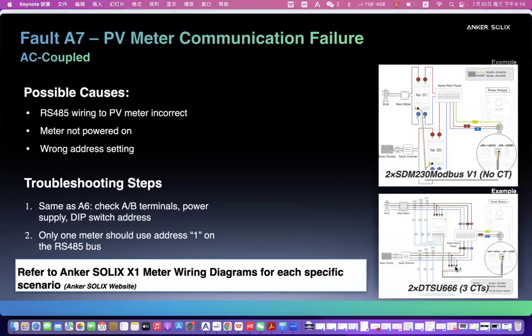It will show A7 when you connect it wrong, because we have the 11 and 12 ports on the meter. The PV communication cable connects to this place. Make sure 11 connects to the 485 plus and 12 connects to the 485 minus. So it should be corresponding. If it's wrong, it shows this error. Yeah, similar to this scenario.